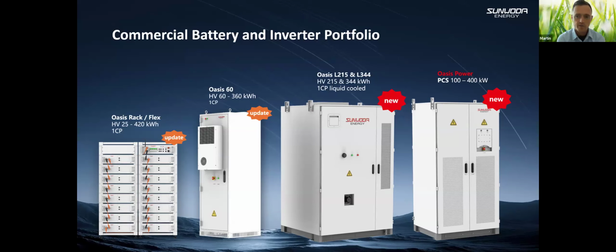What this product specifically speaks to is safety—that's the most important aspect of our design philosophy; we want to make it as safe as possible, and also as easy as possible to install. Everything is pre-wired and prefabricated, so you drop the unit on site and can immediately install your hybrid charger or PCS, commissioning these systems very quickly. From a deployment point of view, that's a massive advantage.